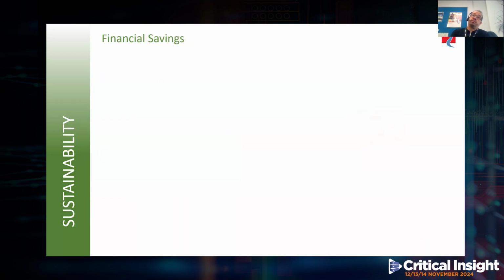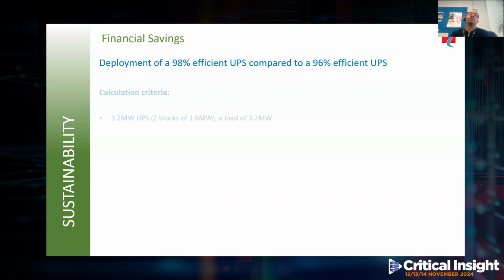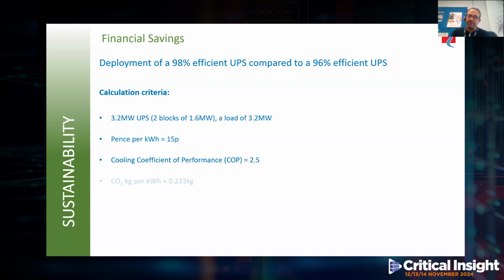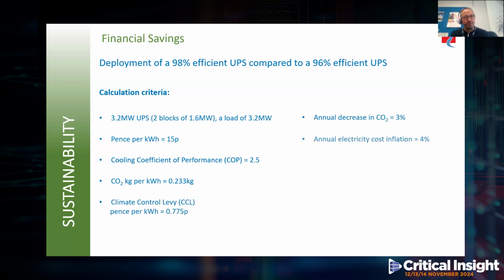Now, we cannot look at the gains, obviously, without looking at the potential financial and CO2 savings. So, as an example, if we deployed a 98% efficient UPS instead of a 96% efficient UPS, and only looked at the UPS heat loss and the cooling power requirements, using a typical 3.2 megawatt UPS system comprising two 1.6 megawatt blocks with a load of 3.2 megawatts, we can see that based on a calculation criteria, so there's a lot of numbers here, so here goes: a cost per kilowatt hour of 15 pence, a cooling coefficient of performance of 2.5, a CO2 per kilowatt hour of 0.233 kgs, a climate change levy of 0.775 pence per kilowatt hour, an annual decrease in electricity CO2 production of 3%, and an electricity cost inflation of 4%. I've not included any reactive power charges or any maintenance costs.